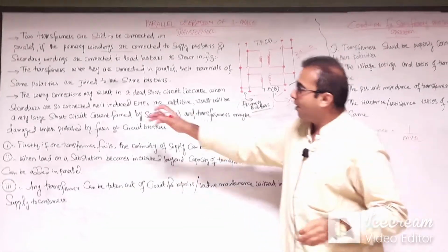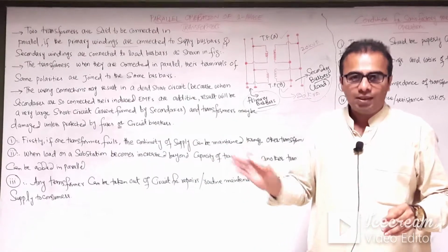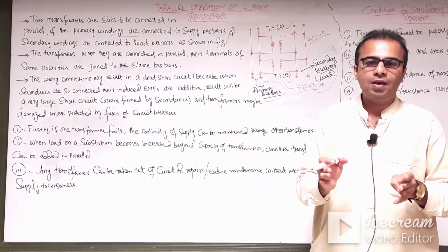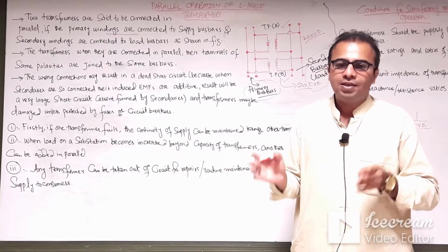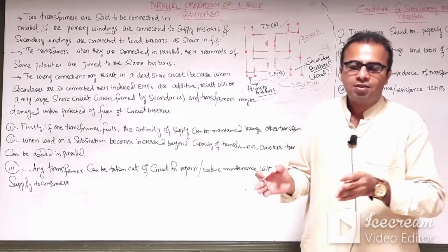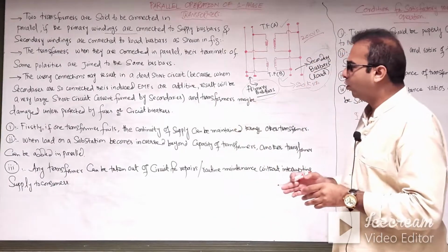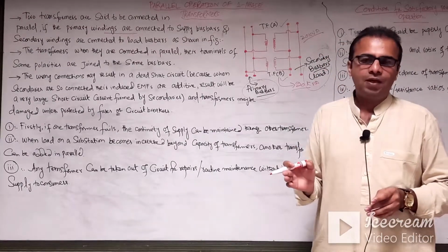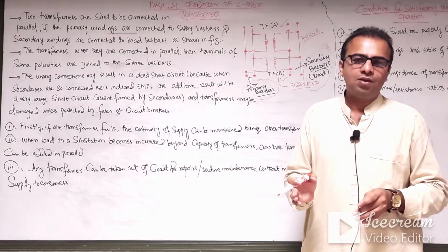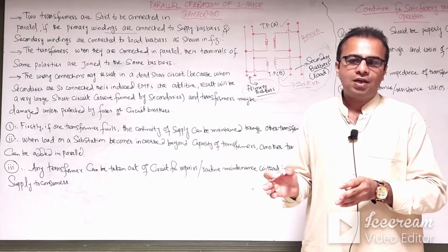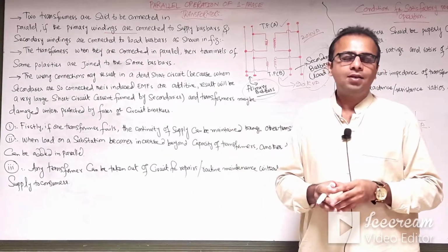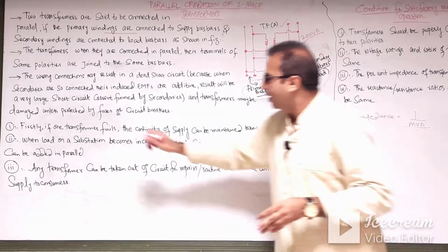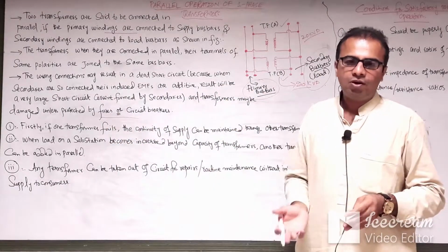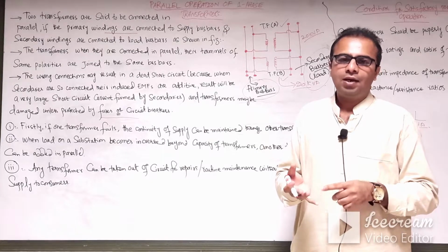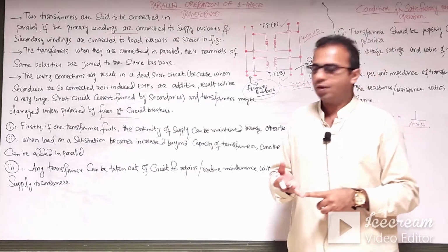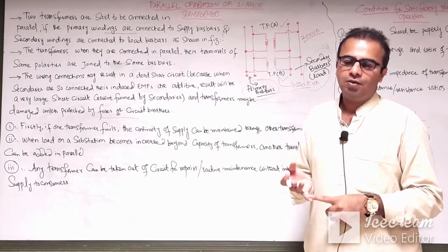If there is a wrong connection, or if the transformers are connected in opposite polarity, the result may be a dead short circuit, or a large short circuit current may flow through the secondaries of the transformers and may cause harmful effects on the transformers, unless the transformers are protected with the help of protective devices like circuit breakers or fuses. These are protective devices like circuit breakers. They are going to trip the electrical machines, and the fuses are also protective devices.